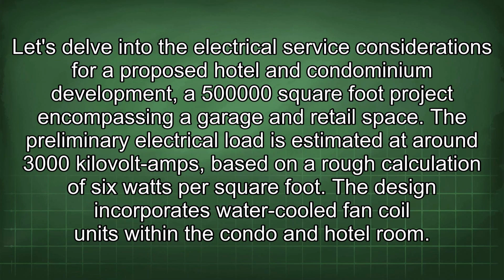Let's delve into the electrical service considerations for a proposed hotel and condominium development, a 500,000 square foot project encompassing a garage and retail space. The preliminary electrical load is estimated at around 3,000 kilovolt amps, based on a rough calculation of 6 watts per square foot. The design incorporates water-cooled fan coil units within the condo and hotel room.